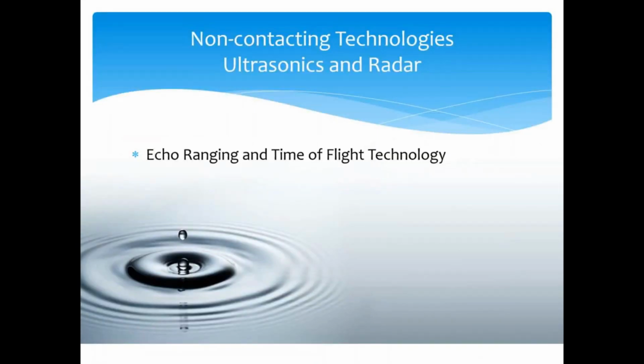So one of the things that we're going to really focus on today is when we debate whether we should be using ultrasonic or radar as our technology of choice for measuring level, allowing the application to choose the technology for us. And the acronym that we use for that is STAMP. So we're going to look at the size of the tank or the vessel, the temperature and the pressure inside the tank or the vessel, what the media is that we're measuring, and then the atmosphere within that tank or that vessel. And these steps or these guidelines are really going to dictate for us which technology makes the most sense for your given application.